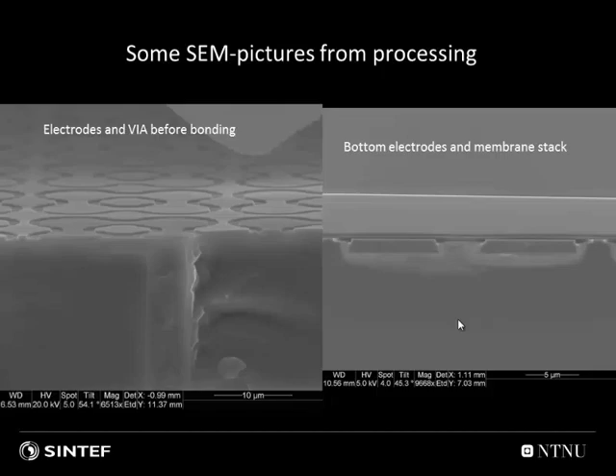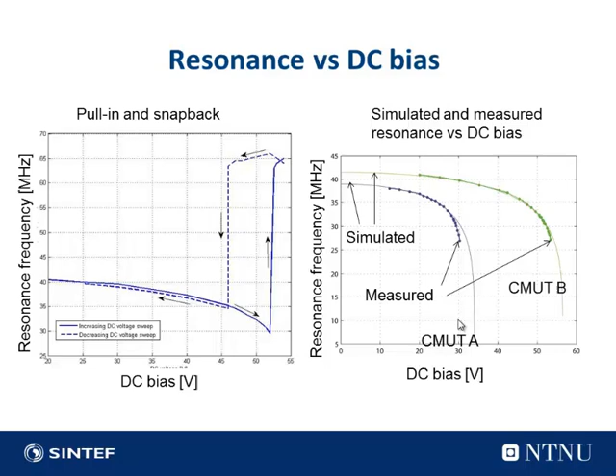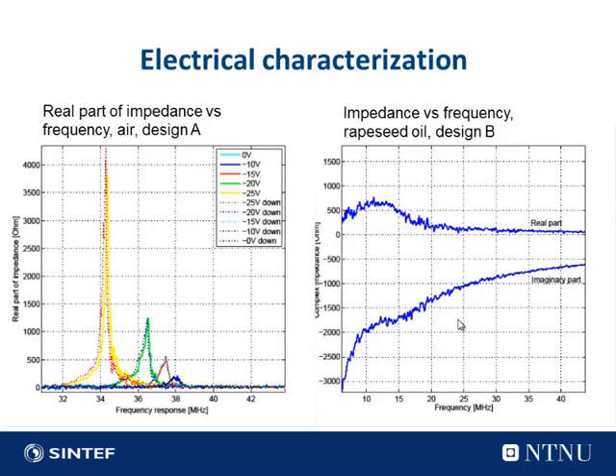For the measurements, we have done a measurement of pull-in and snapback behavior to find the pull-in voltage. We have done measurements at different DC bias. We didn't quite get the resonance frequency to correspond with the simulations. We believe it's because we haven't met the correct material parameters, but by changing the material parameters we got a quite good match, though that was after the fabrication. Since I'm focused on this one, these are the measurements in rapeseed oil. It has pretty much the same acoustic properties as blood, so that's why we have chosen that. We reached 12 megahertz resonance, which is a bit lower than we wanted, but we still think it's possible.